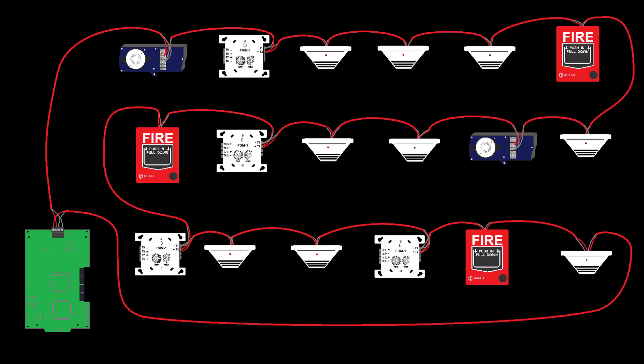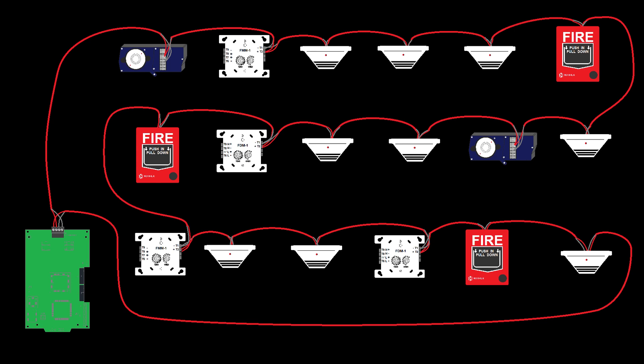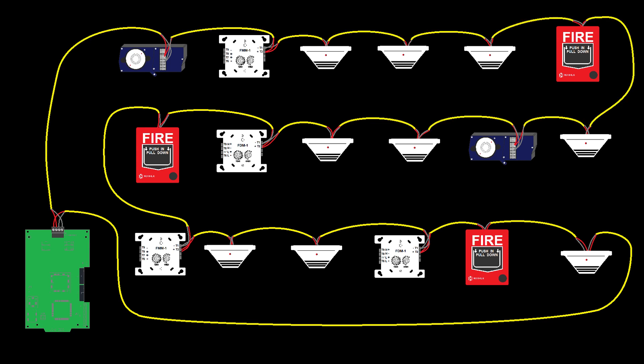All of our loops will be configured as style 6, which simply means a Class A SLC loop. For an SLC circuit to be style 6, it will leave the panel, go into and out of each device in series, and return back to the panel with no T-taps.